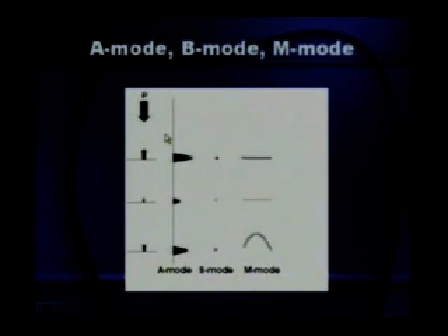The earliest mode of echo that was developed was the A mode. What was done in this was that every echo was displayed in the form of a spike, and the length or height of the spike was proportional to the intensity of the echo signal received. In this example, these are the 3 structures that are reflecting the ultrasound beam. This is the position of the probe or transducer. The ultrasound beam is coming in this direction and is getting reflected. This structure reflects maximum ultrasound waves. This is reflecting relatively fewer waves, and this is in between these two. So in A mode, this signal will be displayed in the form of a spike. This is displayed here, and ultrasound beams which are being reflected from this are displayed here. The amplitude or height of these 3 spikes is proportional to the intensity of the ultrasound signal that is being received.